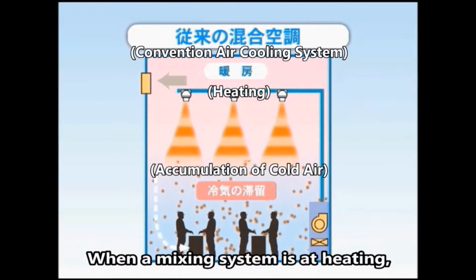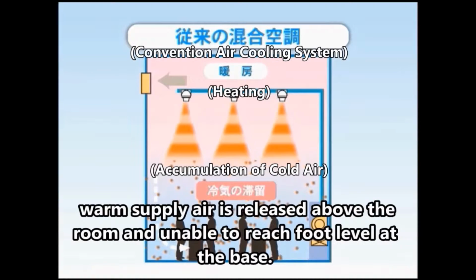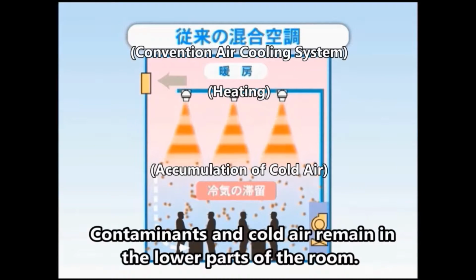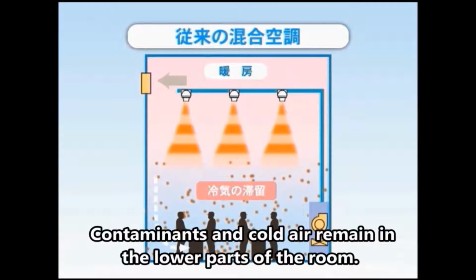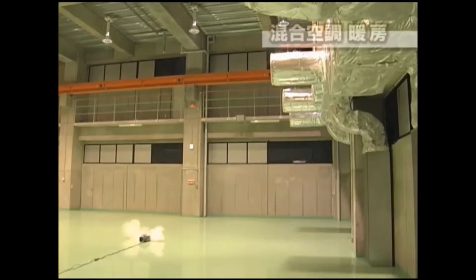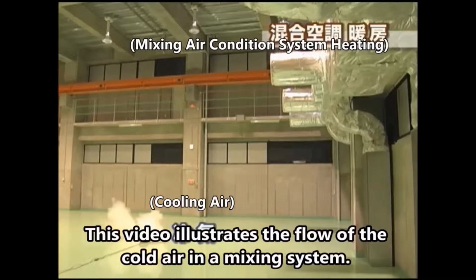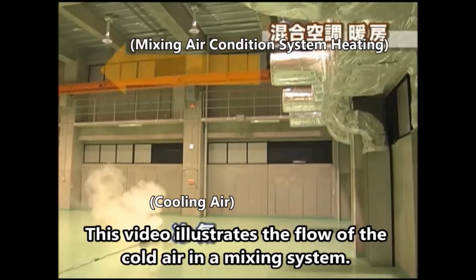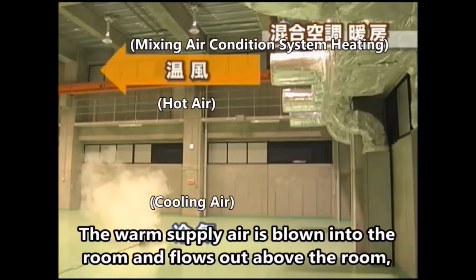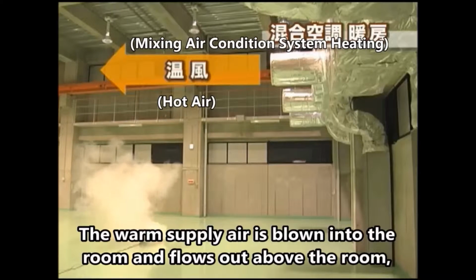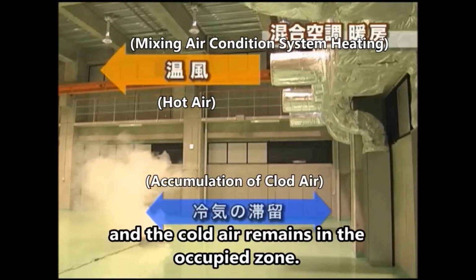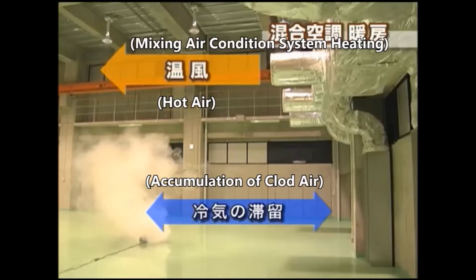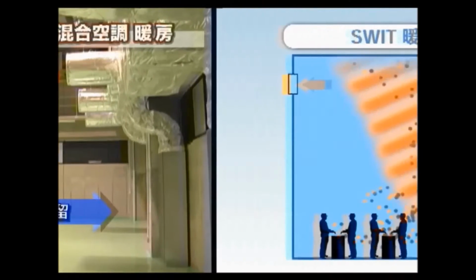Warm supply air is released above the room and is unable to reach foot level at the base. Contaminants and cold air remain in the lower parts of the room. The warm supply air is blown into the room and flows out above the room, and the cold air remains in the occupied zone.